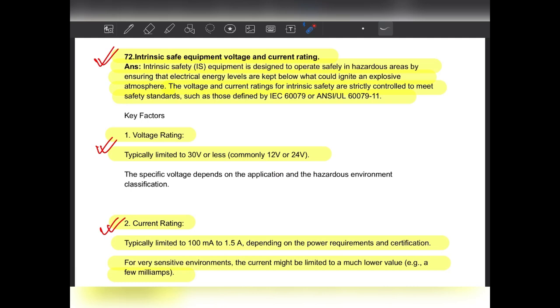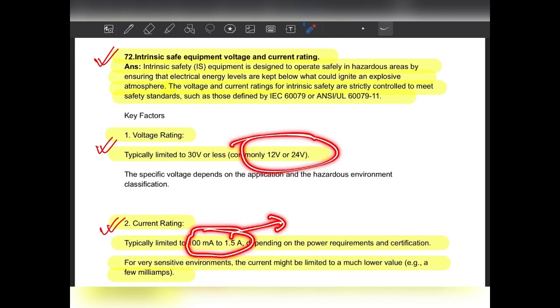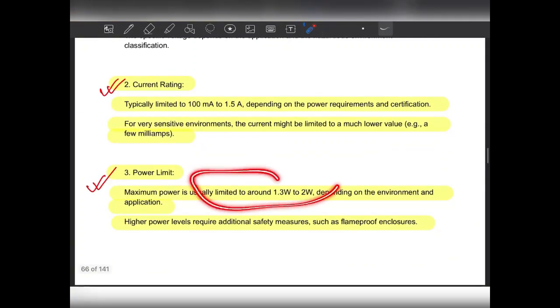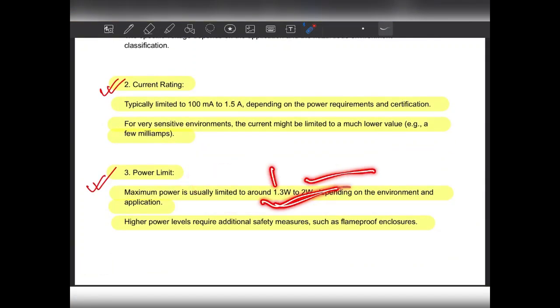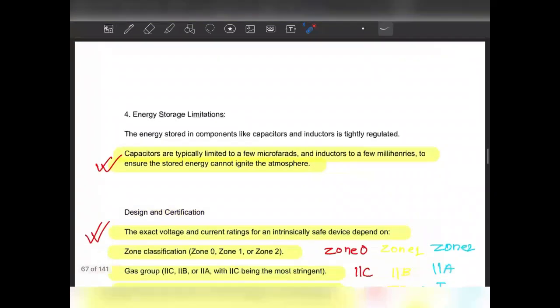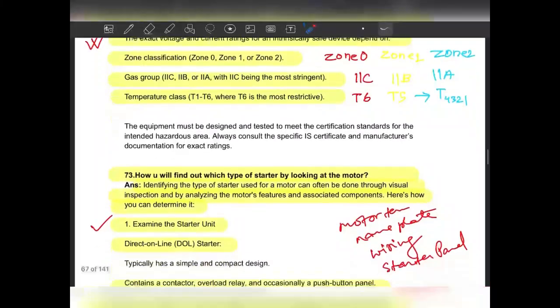For voltage and current rating, we basically use 30 volt, and we use voltage between 12 volt and 24 volt, and current from 100 milliampere to 1.5 ampere. We use very little current because it will not create any spark, and the voltage is also very low. We also limit power to 1 watt to 2 watt, or 1.3 watt to 2 watt. Whatever it is, the power limit is very low. So these are basically the current ratings and all this.